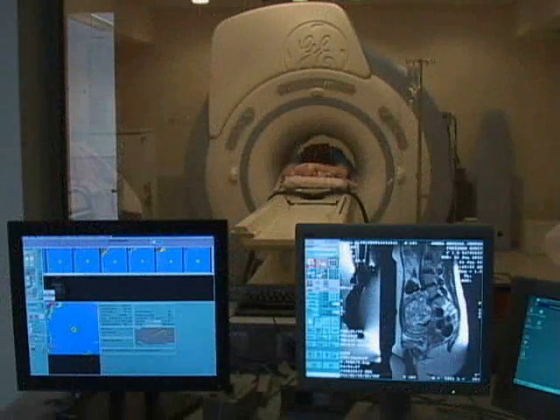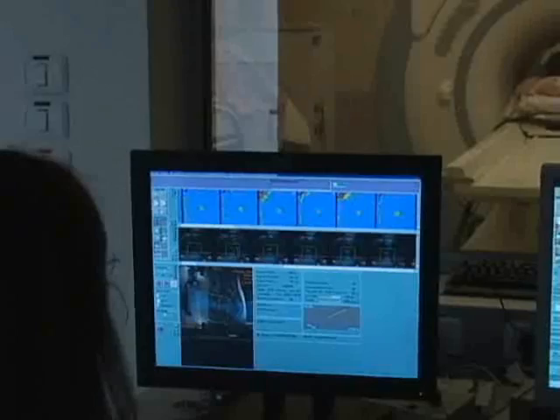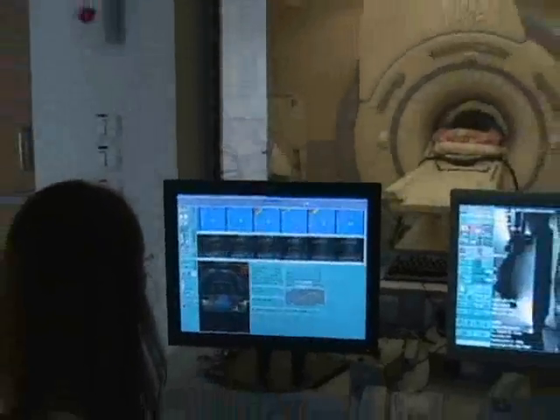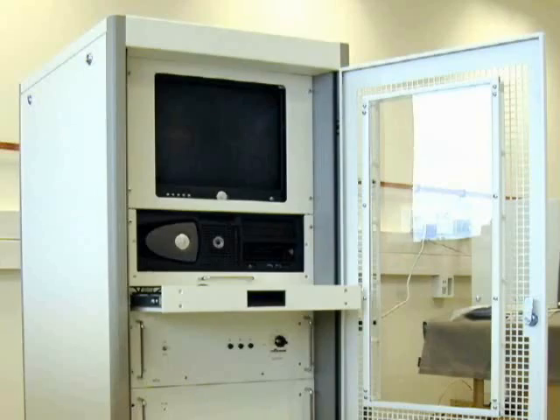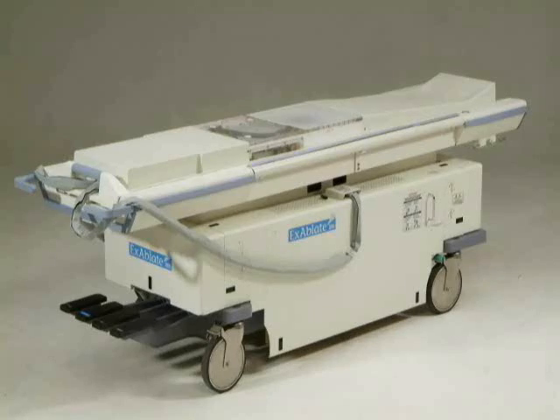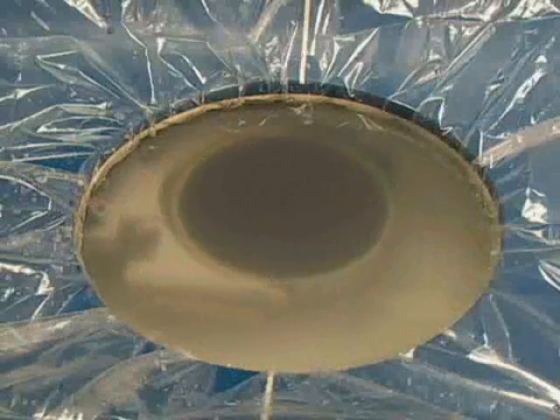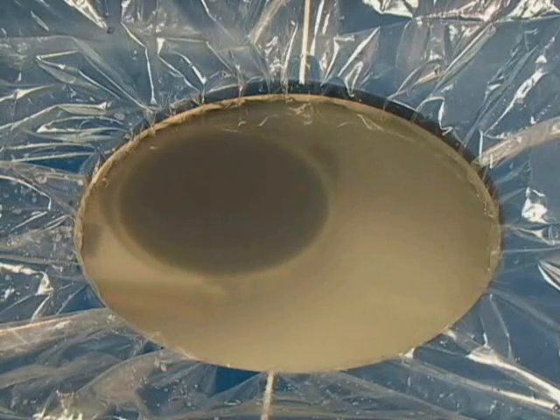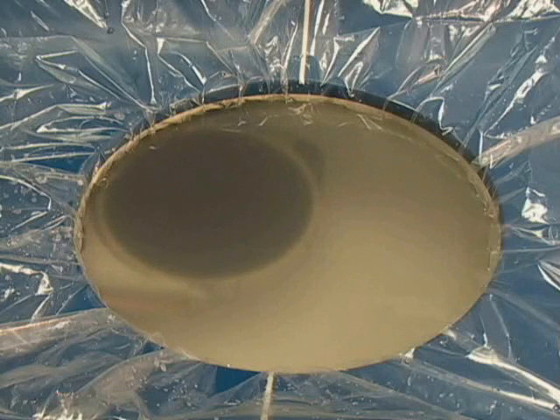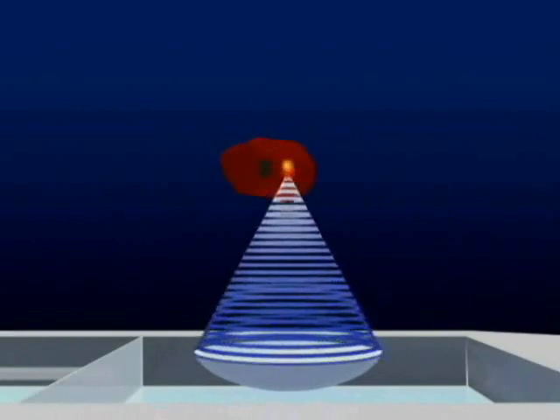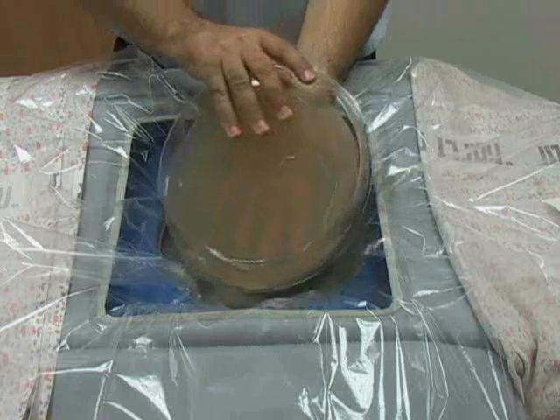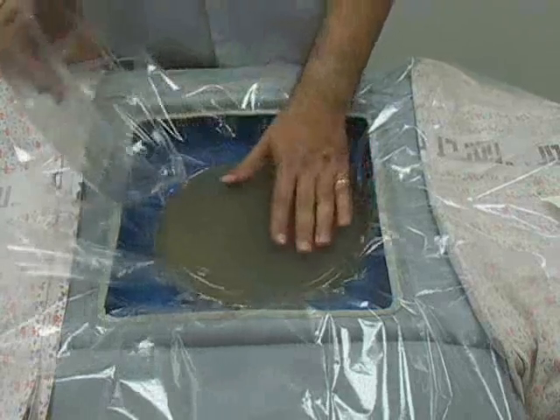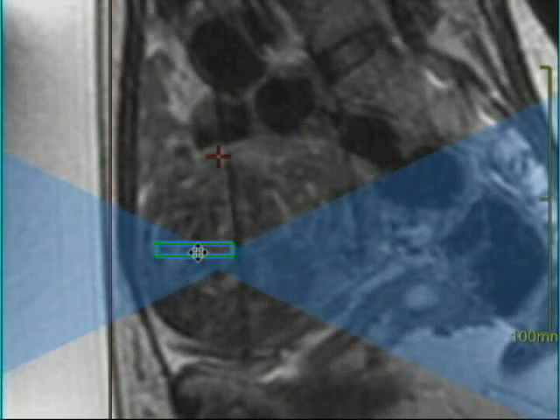Exablate 2000 consists of 3 components. A workstation, which sits alongside the GE MR console, an electronics cabinet, which resides in the MR equipment room, and a patient table with a movable transducer. The ultrasonic transducer is immersed in a sealed liquid bath and is moved and tilted by a positioning system which moves back and forth, and rolls, and tilts. The transducer generates the beam of focused energy which passes through the liquid bath and acoustic coupling gel pad to reach the targeted tissue without affecting the surrounding organs. The depth of focus in the body is controlled electronically.